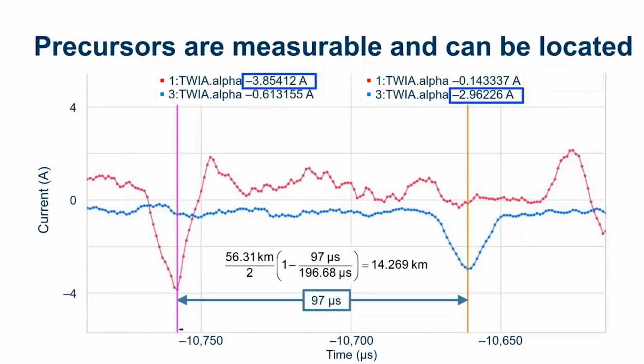Now, as I said before, if we've got an internal fault, the traveling waves should be in the same polarity. And so our precursor is showing that we have traveling waves in the same direction. The traveling wave line propagation time isn't shown on this slide, but these both arrive in less than our traveling wave line propagation time. You can see that our current here is very low, but we're still calculating a distance to the fault. Now, I don't have the next slide.